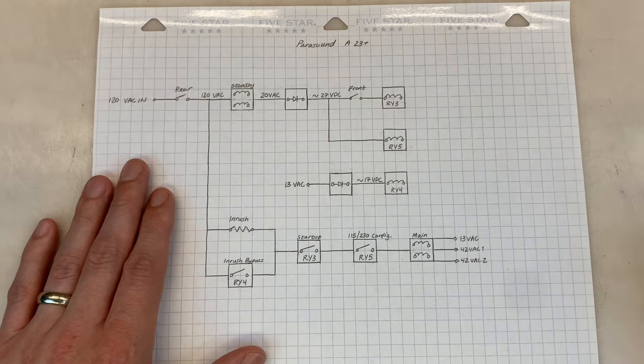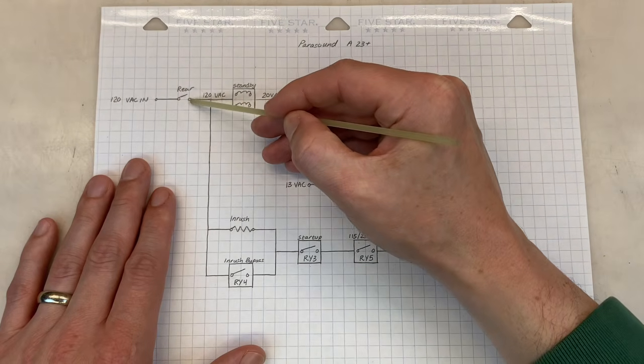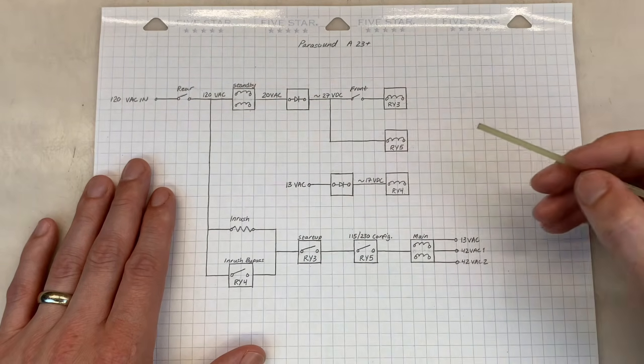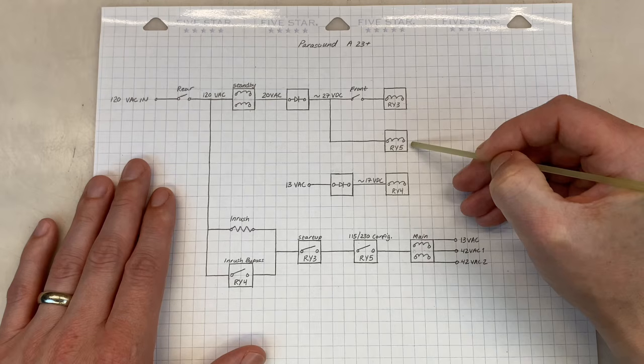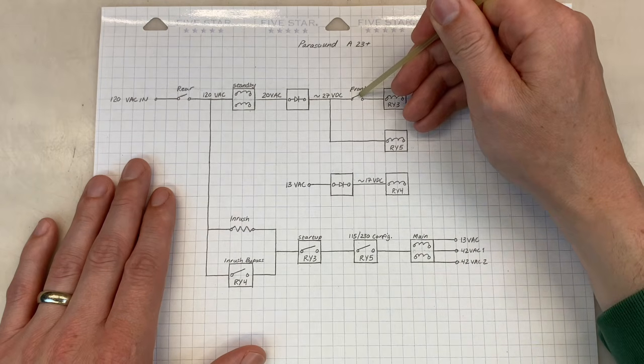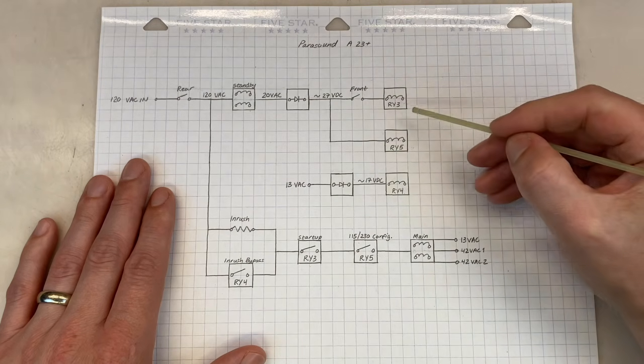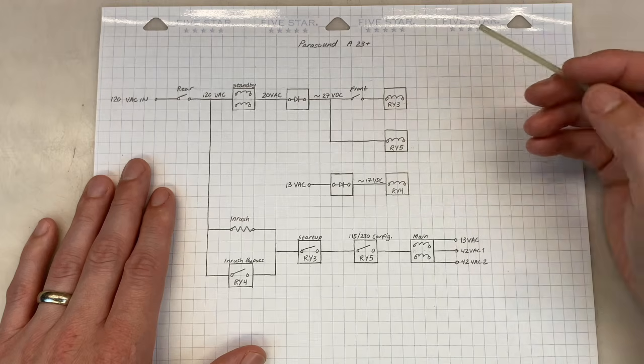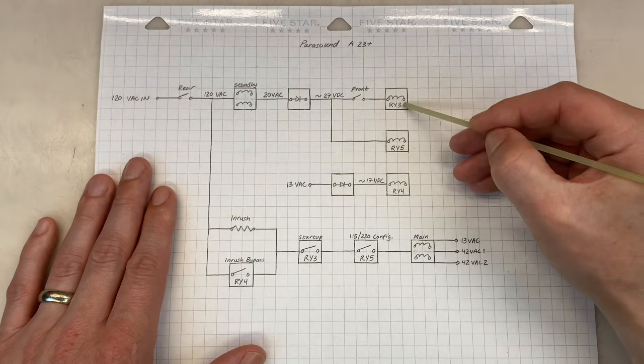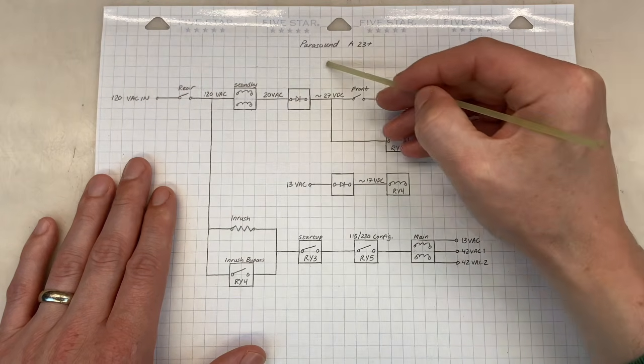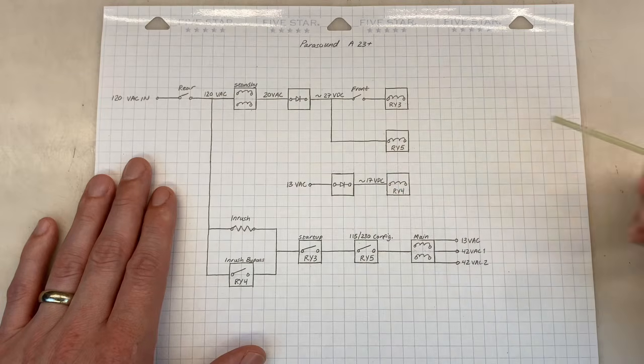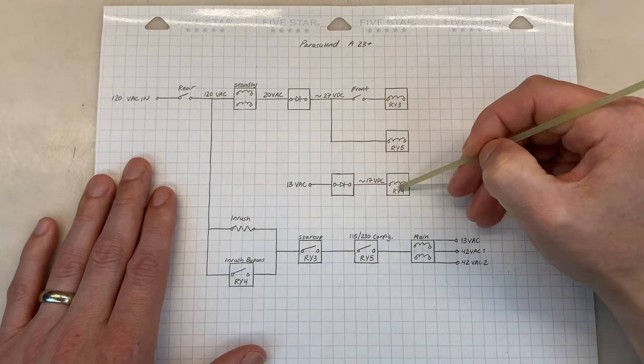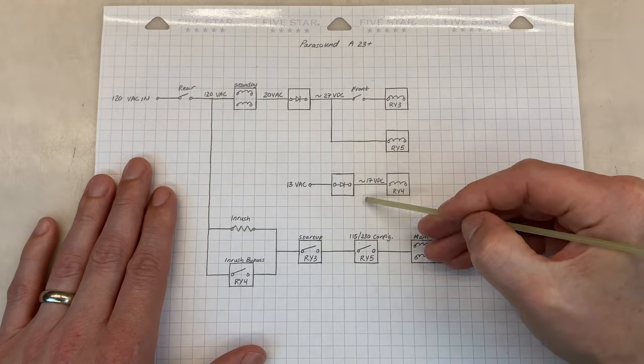But what did I see and measure? When I turned the rear switch on, I heard the audible click. That would have been relay RY5 being energized. When I turned the front switch on, I heard another audible click, which would have been relay RY3 being energized. Not only that, but I did measure voltage at both coils, indicating this entire section of the circuit was working properly. From there, I looked for DC voltage at the coil of relay RY4, so here, and saw nothing.